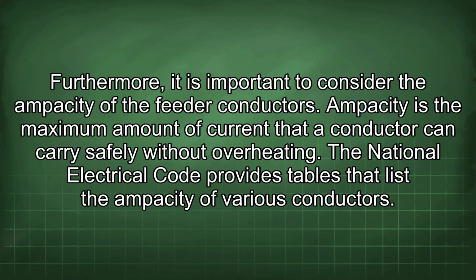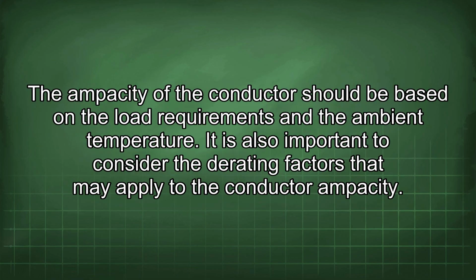Furthermore, it is important to consider the ampacity of the feeder conductors. Ampacity is the maximum amount of current that a conductor can carry safely without overheating. The National Electrical Code provides tables that list the ampacity of various conductors. The ampacity of the conductor should be based on the load requirements and the ambient temperature.